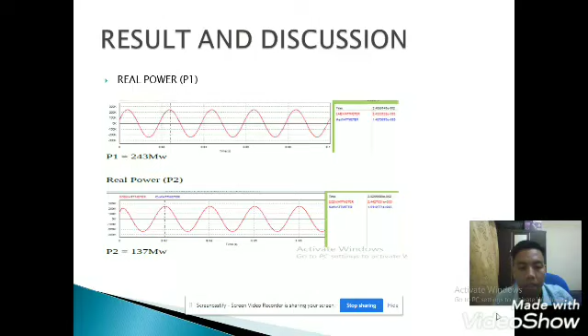The power factor is 0.9 lagging, so cos inverse of 0.9 is 25.8419. Power measured by the first wattmeter, W1, is equal IL multiplied with VL cos of 30 minus 25.8419, which equals 243 megawatt.